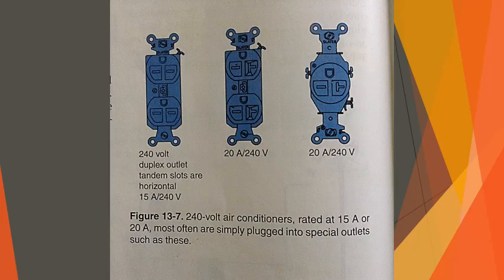Room air conditioner units. Air conditioners are connected from either 120 or 240 volts and generally are rated between 4 and 10 amperes. For example, a typical air conditioner may be rated at 1.5 kilovolt amps, or kVAs, 240 volts times 6.25 amps. This air conditioner could be placed on a 15 amp double pole breaker or plugged into a receptacle like the one shown in figure 13-7.